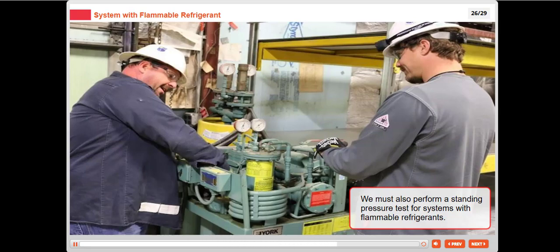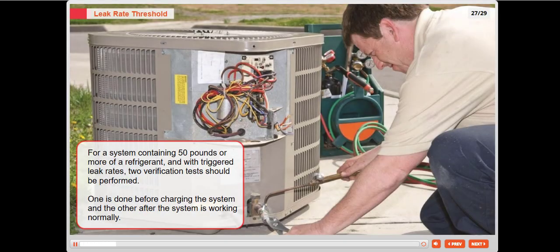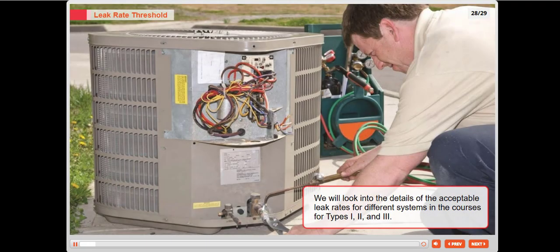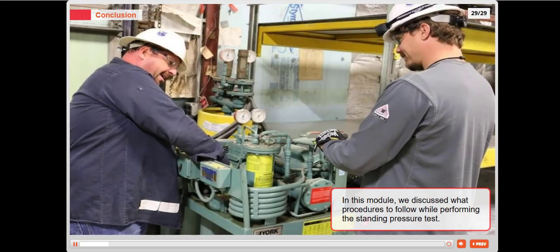For a system containing 50 pounds or more of a refrigerant, and with triggered leak rates, 2 verification tests should be performed. One is done before charging the system and the other after the system is working normally. We will look into the details of the acceptable leak rates for different systems in the courses for types 1, 2, and 3. In this module, we discuss what procedures to follow while performing the standing pressure test.